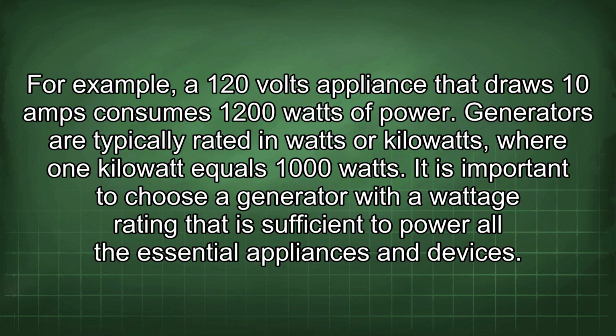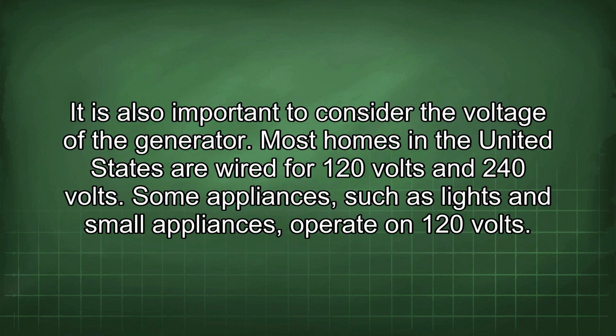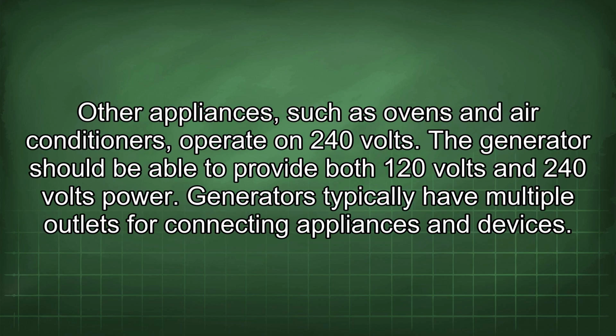It is important to choose a generator with a wattage rating that is sufficient to power all the essential appliances and devices. It is also important to consider the voltage of the generator. Most homes in the United States are wired for 120 volts and 240 volts. Some appliances, such as lights and small appliances, operate on 120 volts. Other appliances, such as ovens and air conditioners, operate on 240 volts. The generator should be able to provide both 120 volts and 240 volts power.